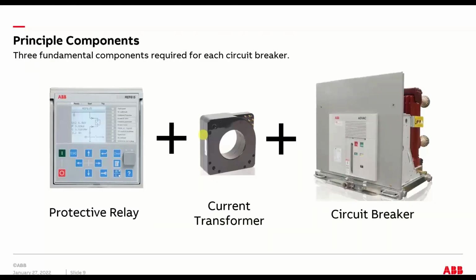Fundamental, the basic parts we already discussed are the relay itself. This is an example of an ABB numerical relay, current transformer, and circuit breaker. So you need at least these three pieces to make a complete circuit breaker system. And this circuit breaker is a vacuum breaker used for medium voltage switchgear. But it could be a whole slew of different breaker technologies, sizes and configurations. This is more of a medium voltage metal clad switchgear example.